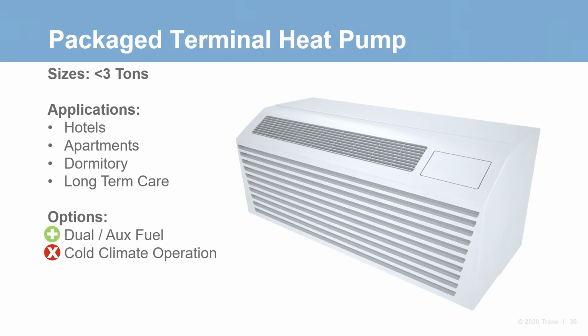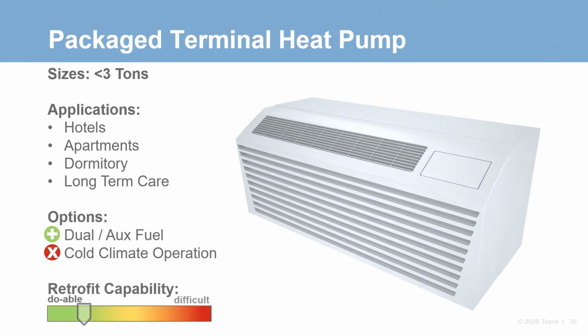Typical operation is going to be just based on the outside air temp. When the temperature goes below 32 degrees, the heat pump turns off and the electric resistance turns on. For cold climate locations, this means you'll be sizing your peak heating and electrical loads with 100% electric resistance. However, these products are ideal for electrification retrofits.